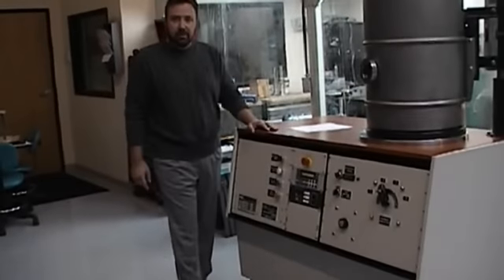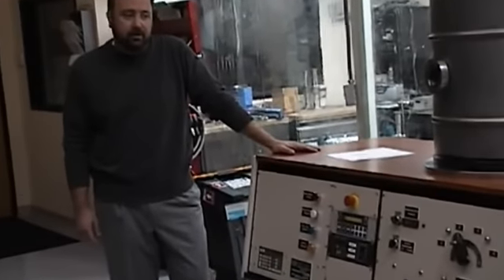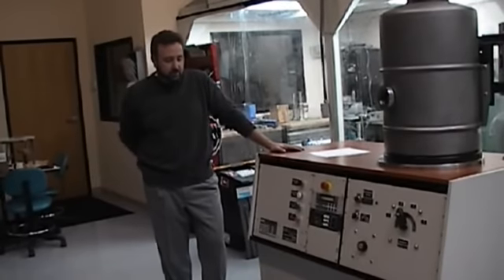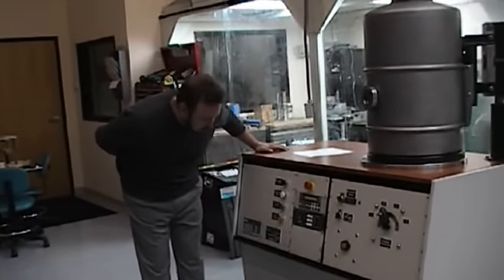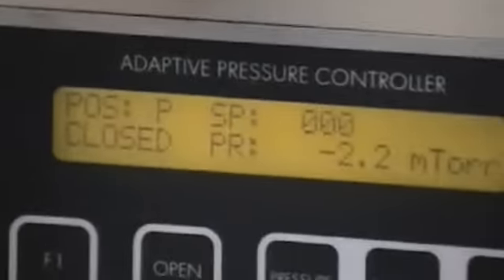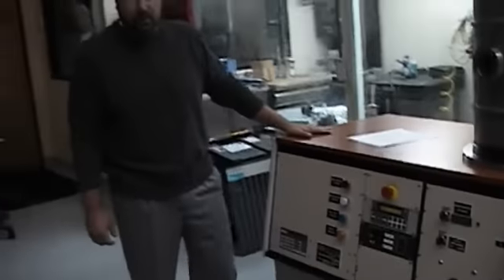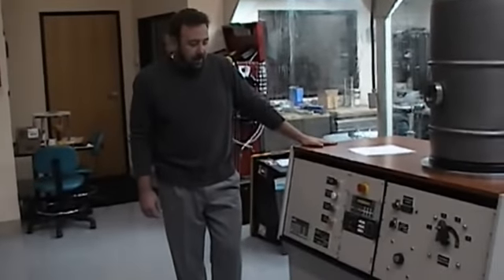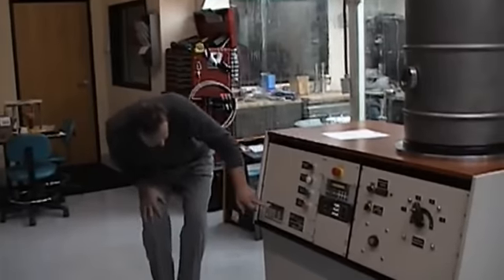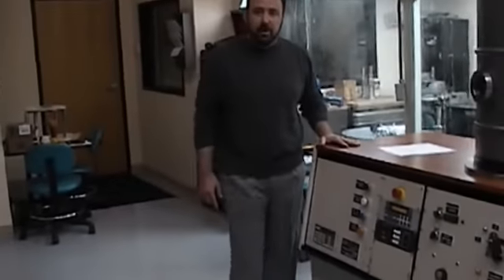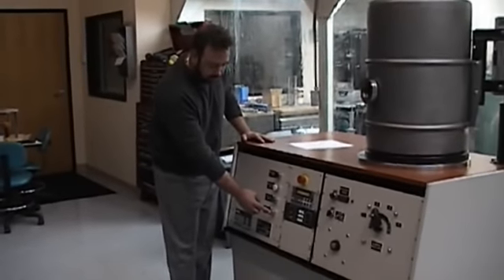At this time, simply de-energize the high vacuum valve and you will close the valve. It is in the closed position. It does tell you what the status is on the PM5 controller. So even though you're working this remotely, it is controlling the valve and telling you where you're at. Right now, our status is 9 Kelvin on the cryo pump. All valves closed, all pumps off. We are going to go ahead and vent the chamber, raise the bell jar, and demonstrate.